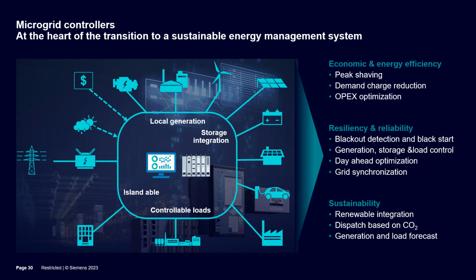When the grid is operating, the local generation—whether gas-fired gen sets, diesel gen sets, solar, wind, or other sources—can operate in parallel with the grid, and the microgrid controller can optimize dispatch based on economics, choosing between grid power and locally generated power, while operating normally. When the microgrid controller senses that the grid is going down for some reason, or there's a disruption in power service, it can open the main breaker and take control of the local assets so there's no interruption in service.